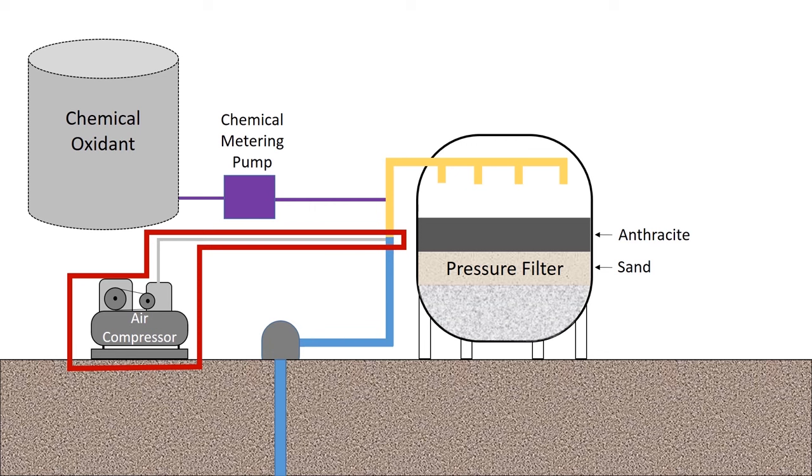So one method is by using air or some form of aeration. Here we have an air compressor, but it could be some other form of aeration where another type of aerator is used to oxidize iron more so than manganese.